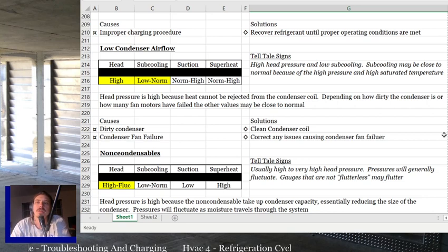Usually, low condenser airflows or dirty condensers don't have very low subcooling, and they usually still cool just fine. Usually the suction side of the system, the evaporator side of the system, does pretty good, but you operate with a high amperage and you operate very inefficiently. So that's the biggest problem with a dirty condenser.